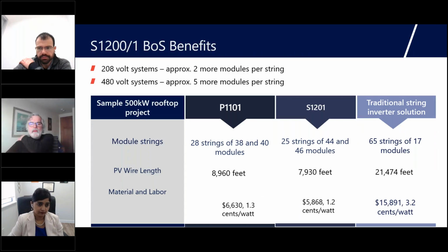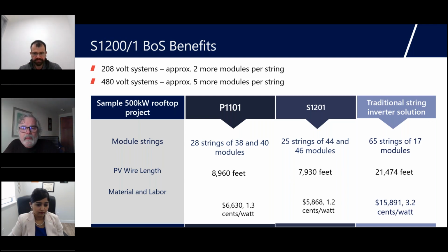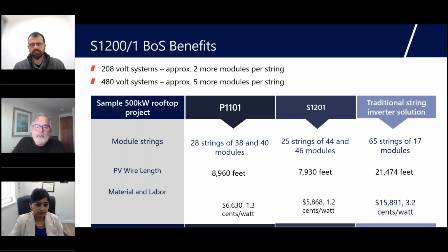So this kind of summarizes some of what we've learned. This was from a BOS comparison we did for a 500 kilowatt rooftop. We compared the SolarEdge 120 kilowatt inverter with a 480 volt grid connection against a competitor's inverter with 1000 volt strings, also 480 volt grid connection. With the P1101, we had half the total quantity of strings compared against a traditional string inverter that was limited to 17 modules per string. So we had 28 strings of 38 and 40 modules versus 65 strings of 17.